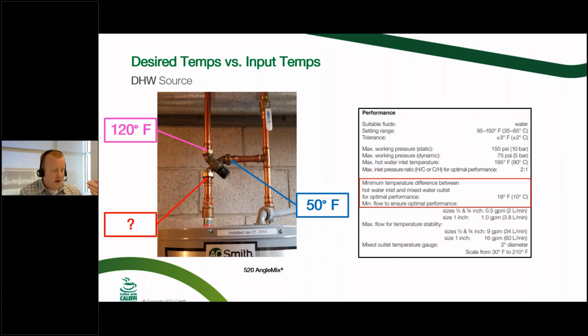Okay, now I'm here to tell you that mixing valves do not produce hot water. They're working with what they've got, and if you don't have the hot water in your water heater, it's not going to be able to magically make hot water. So definitely check your input temperatures. In this case, if you want 120 out of that angle mix there, you're going to need roughly about 138 coming into that mixing valve in order to do that.